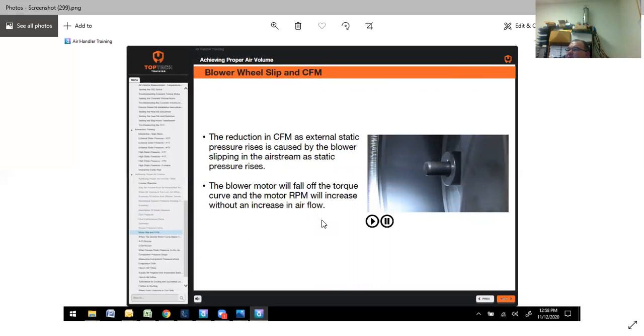The reduction in CFM as external static pressure rises is caused by the blower slipping in the airstream as static pressure rises. Sometimes you can actually hear almost like a pulsing. In the right application, you can almost hear it. It sounds like it's pulsing. The blower motor will fall off the torque curve, and the motor RPM will increase without an increase in airflow. So the motor is spinning faster, but there's no increase in airflow.